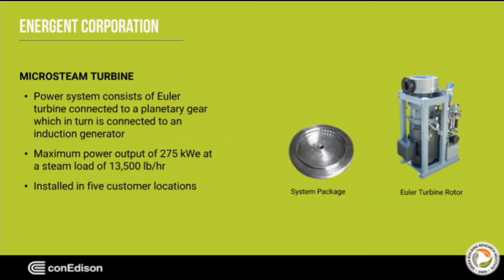ENERGENT Corporation is a California-based company that has 2 products on the market that utilize steam turbine generators. The micro steam turbine, as seen on the right, is a steam turbine generator set that consists of a Euler turbine connected to a planetary gear, which in turn is connected to an induction generator. The Euler turbine is the main component of the set and is a radial outflow turbine designed to handle the saturated steam of similar quality to the steam that is supplied to a customer's building.